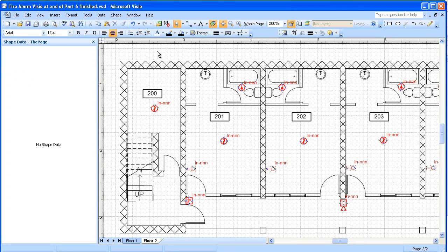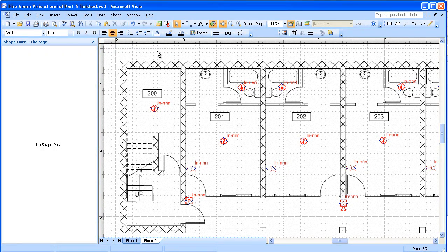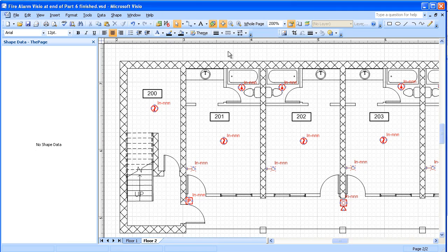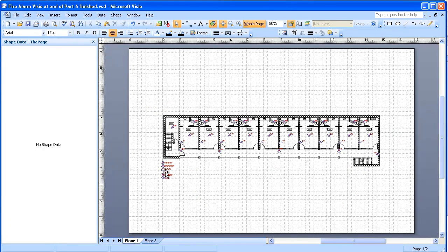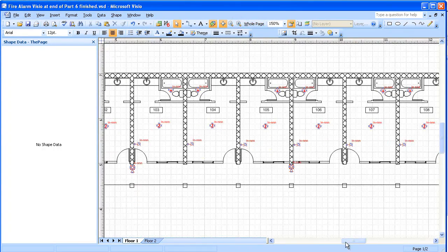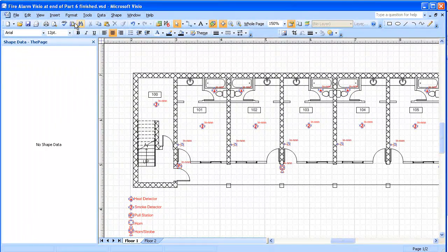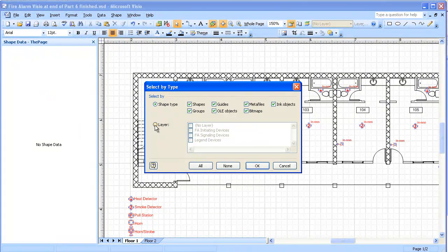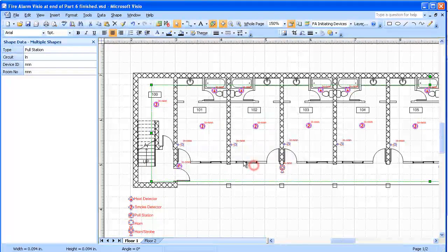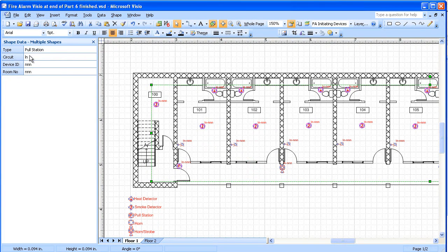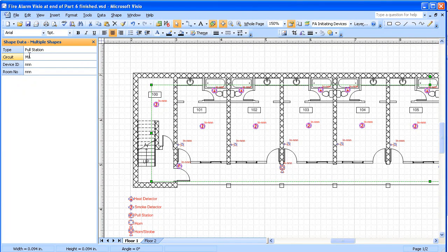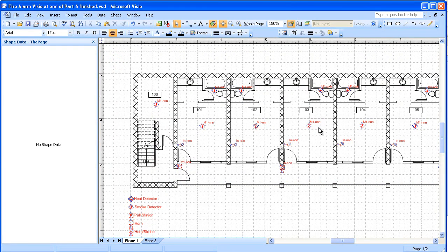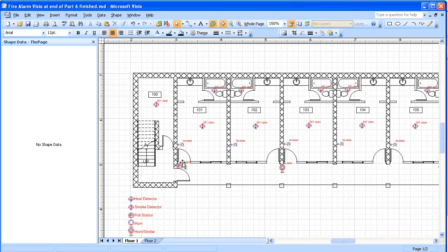My initiating devices, it's a small building, they're going to all be on one circuit. And so I'm going to have a, I'm going to call that circuit M1. So what I will do is, I'm going to go to floor one. And here I will select all of my initiating devices. Select by type, layer, fire alarm initiating devices. And then I'm going to put in for the circuit on that M1. And you'll see that all the names of the M1 has showed up. And this is on all my initiating devices.